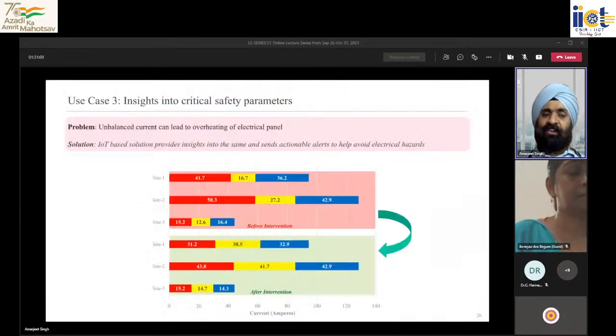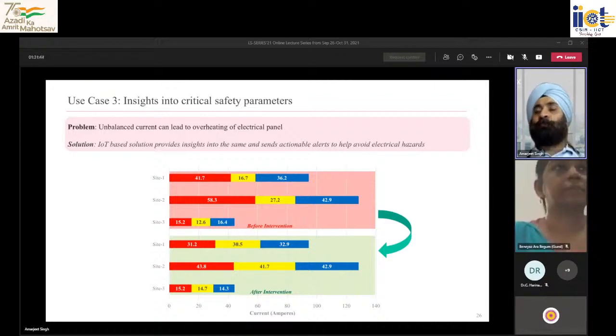Now, data-driven risk detection. For those of you from electrical engineering, you'd know that for a three-phase supply, the loads on each of the phases should be equally distributed so that the current is equal in each phase. Otherwise, the three-phase motors connected to the same supply would have varied power factor and current flowing through each phase, leading to poor winding operation in these motors.